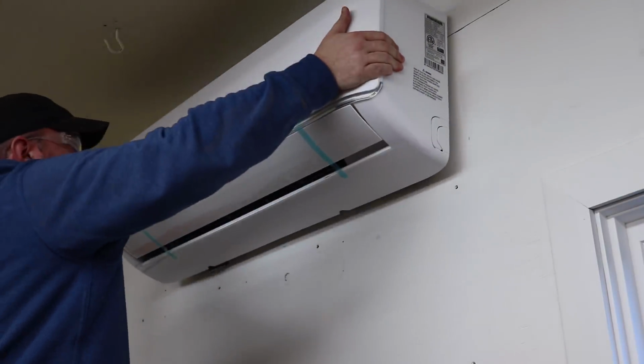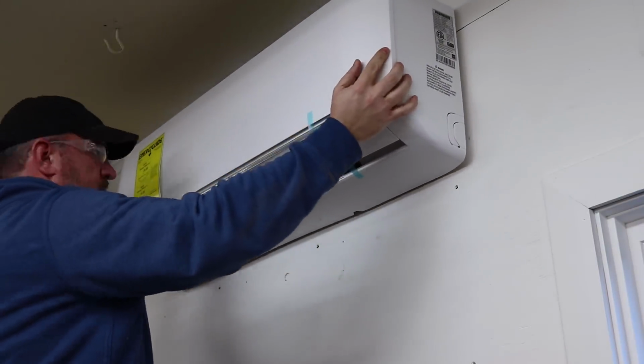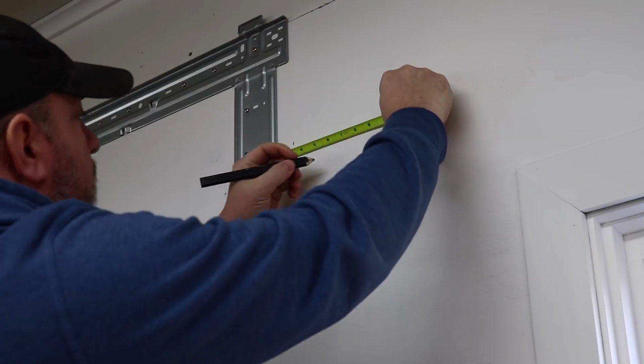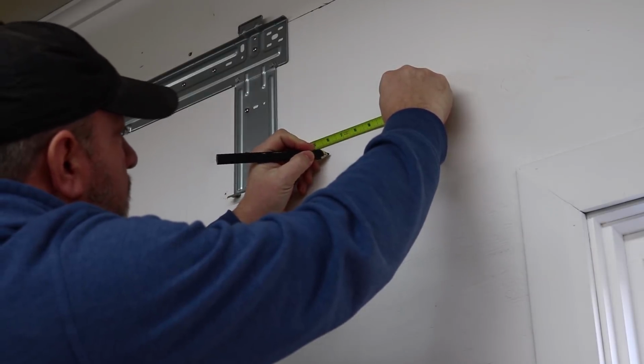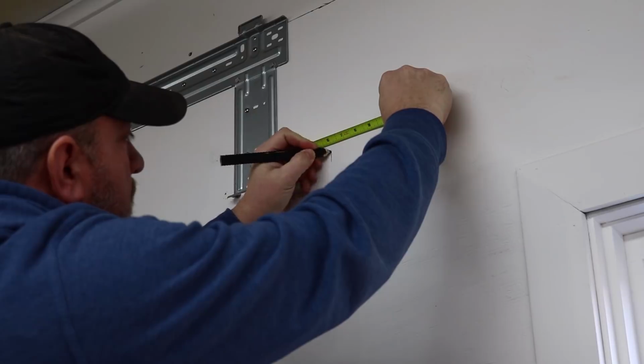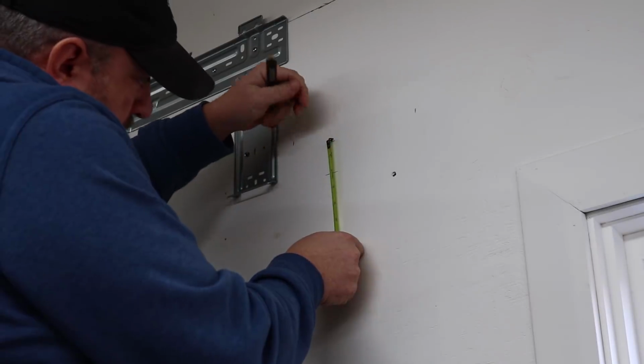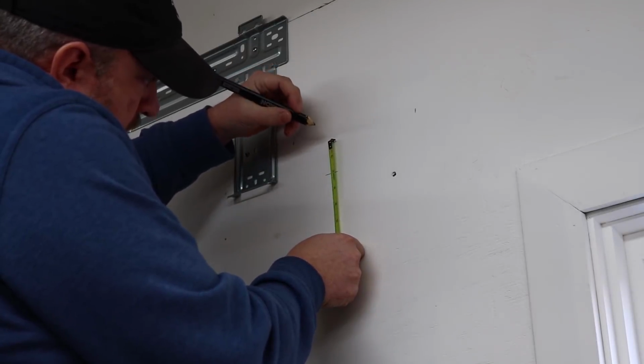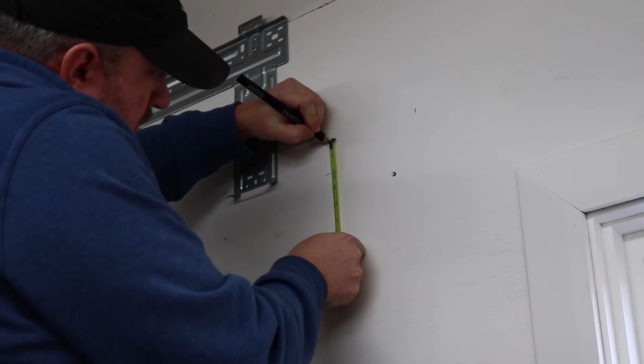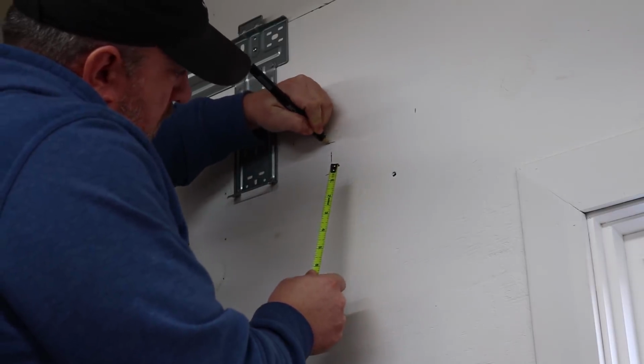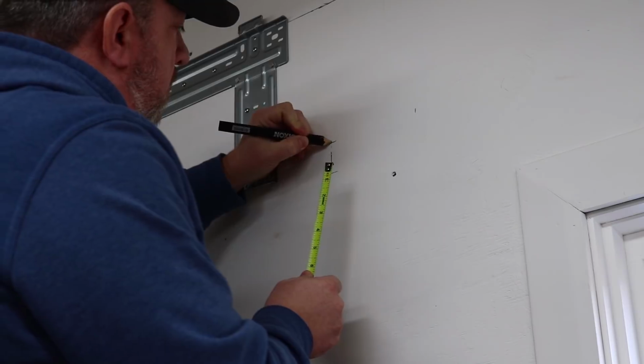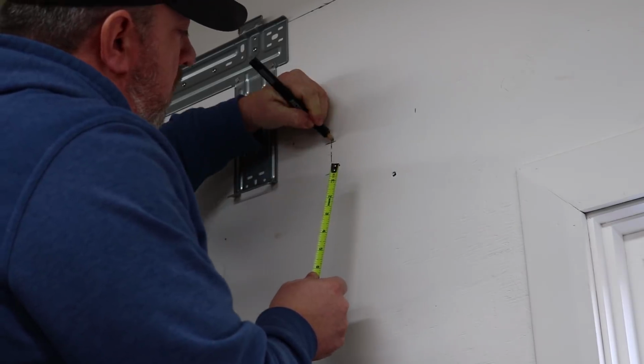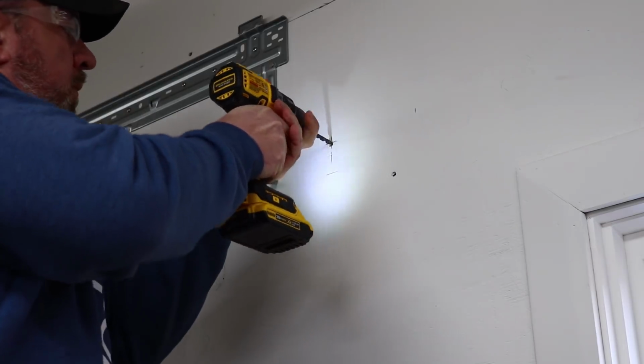With the mounting plate attached, I did a test fitting of the unit just to make sure everything went okay, and then I moved on to marking out the location of the hole to be drilled for the line set to be run through. This unit allows for the line set to be run out either the left or the right side of the unit, or it can be run straight down from the unit along the wall.